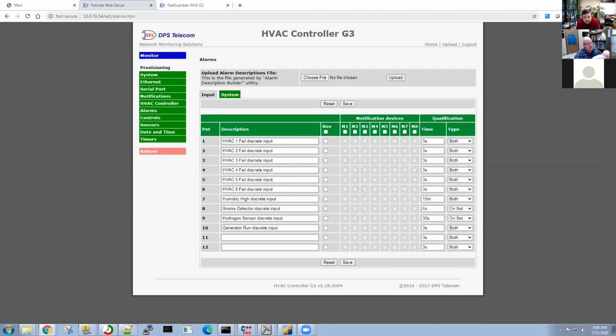The qualification here is basically a way to debounce and keep us from seeing any kind of noise on an alarm line. So if something blips high and blips low - this happens occasionally - we don't need to take action on it until it's been standing there for, in this case, 3 seconds, or in this case, 15 minutes. This qualification time is basically a way to delay alarm input information.